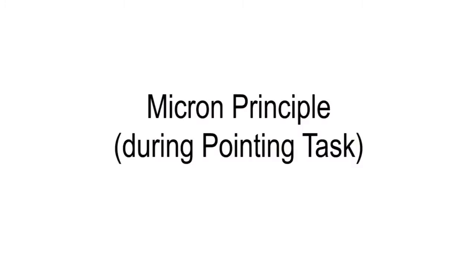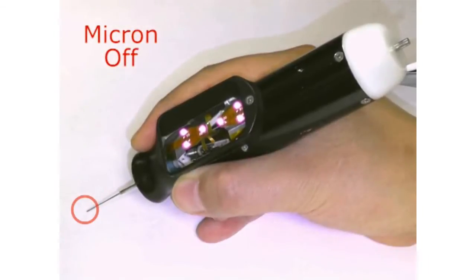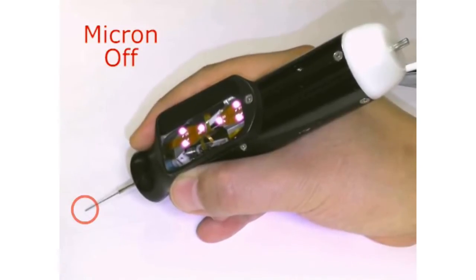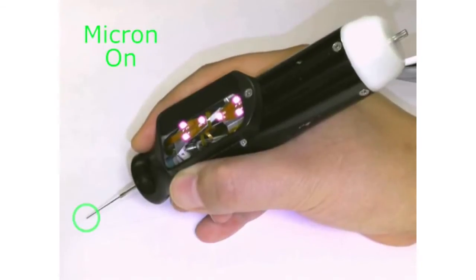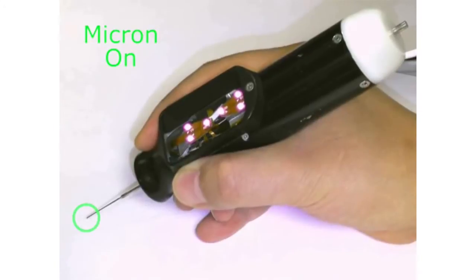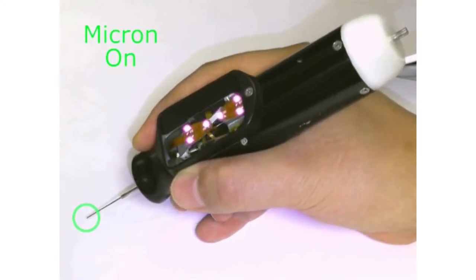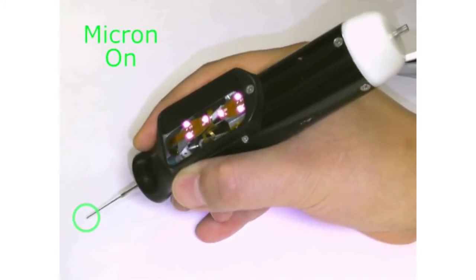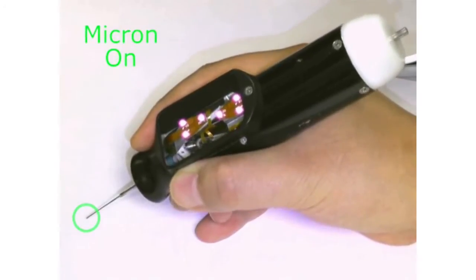This sample video clip demonstrates how Micron operates during a simple pointing task. In unaided operation, the motors are disabled and the handpiece functions as a conventional rigid tool. When cancellation is enabled, the motors are actuated to keep the tip stationary even though the operator's hand is moving, creating the effect of the tip seeming fixed at a point in space despite the motion of the handle. This can be seen most clearly by observing the actuator motion during cancellation.